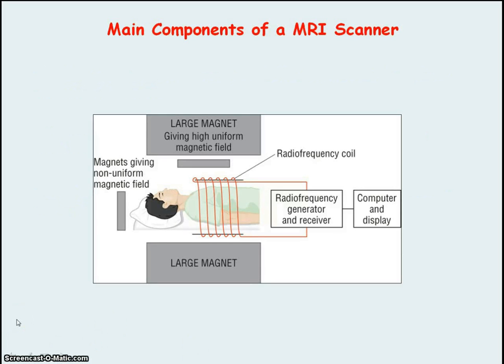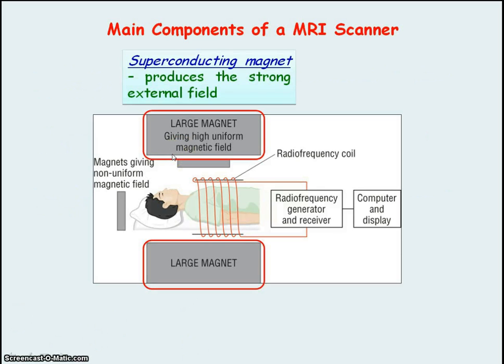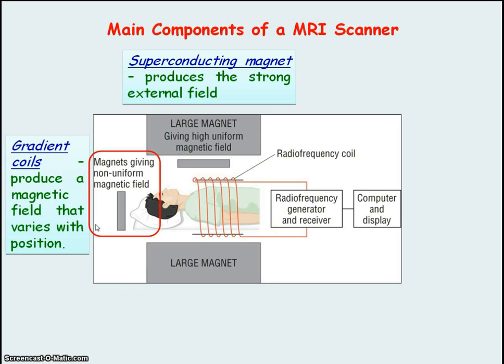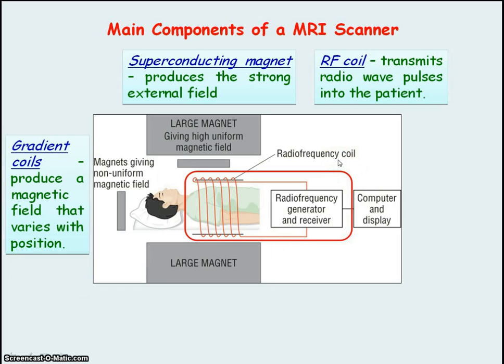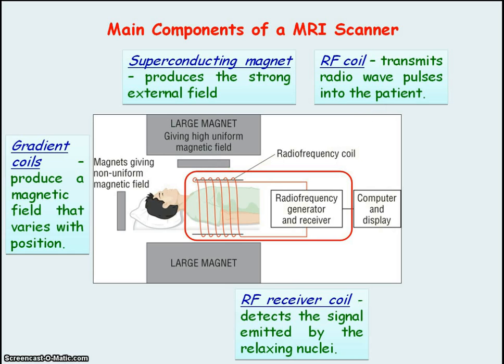There are five main components of an MRI scanner. First, the large superconducting magnet, which produces the strong external field along which the hydrogen nuclei align and precess. You also have gradient coils, which vary the magnetic field across the patient's body. The radio frequency coil transmits the radio wave pulses into the patient, which are absorbed by the hydrogen nuclei, exciting them into the higher energy state. When the RF transmitter coil is switched off, the same coil can act as a receiver and detect the radio frequency signals emitted by the relaxing nuclei.